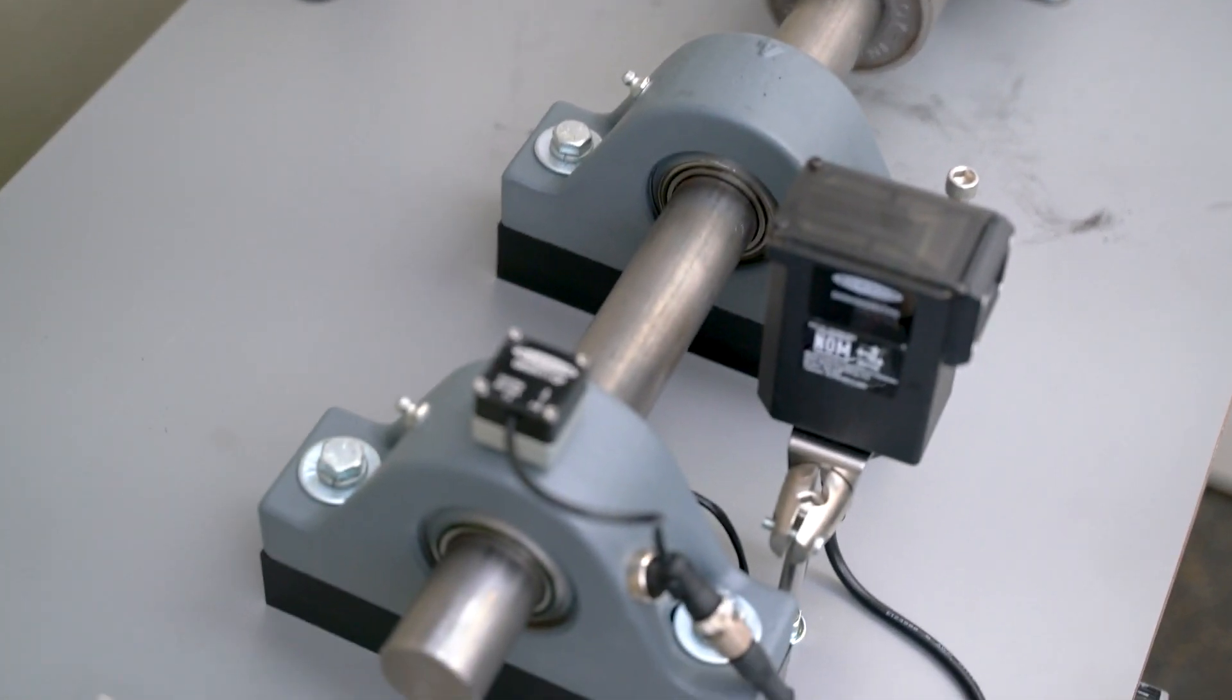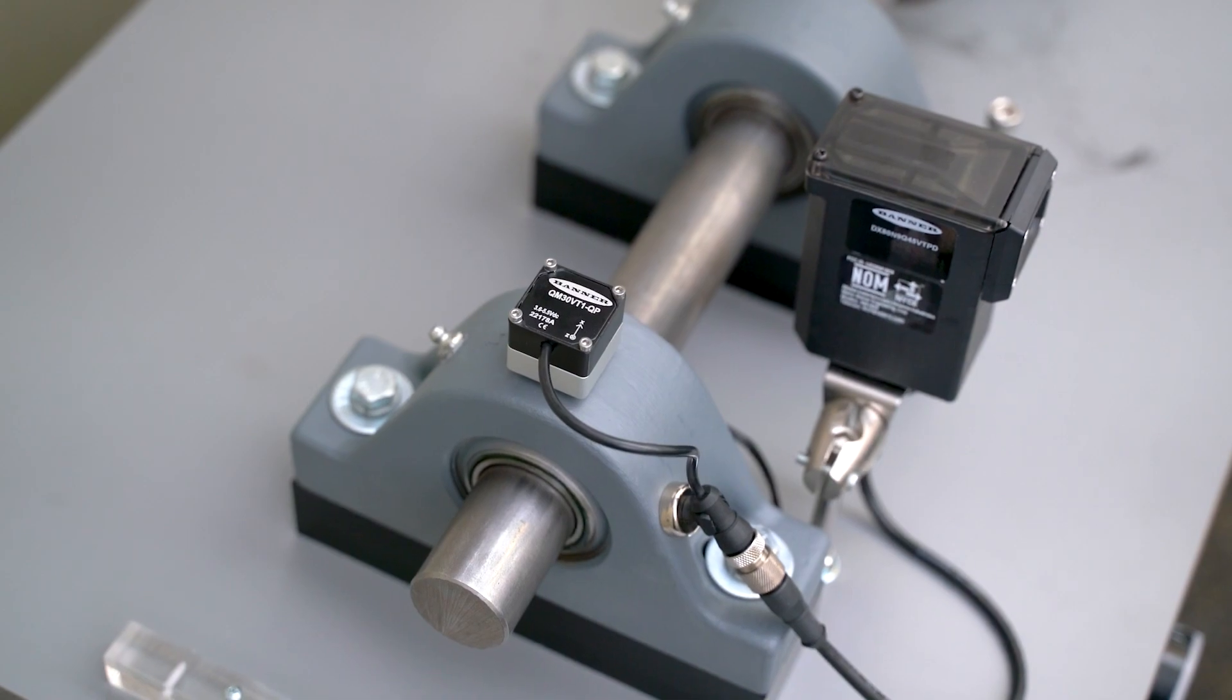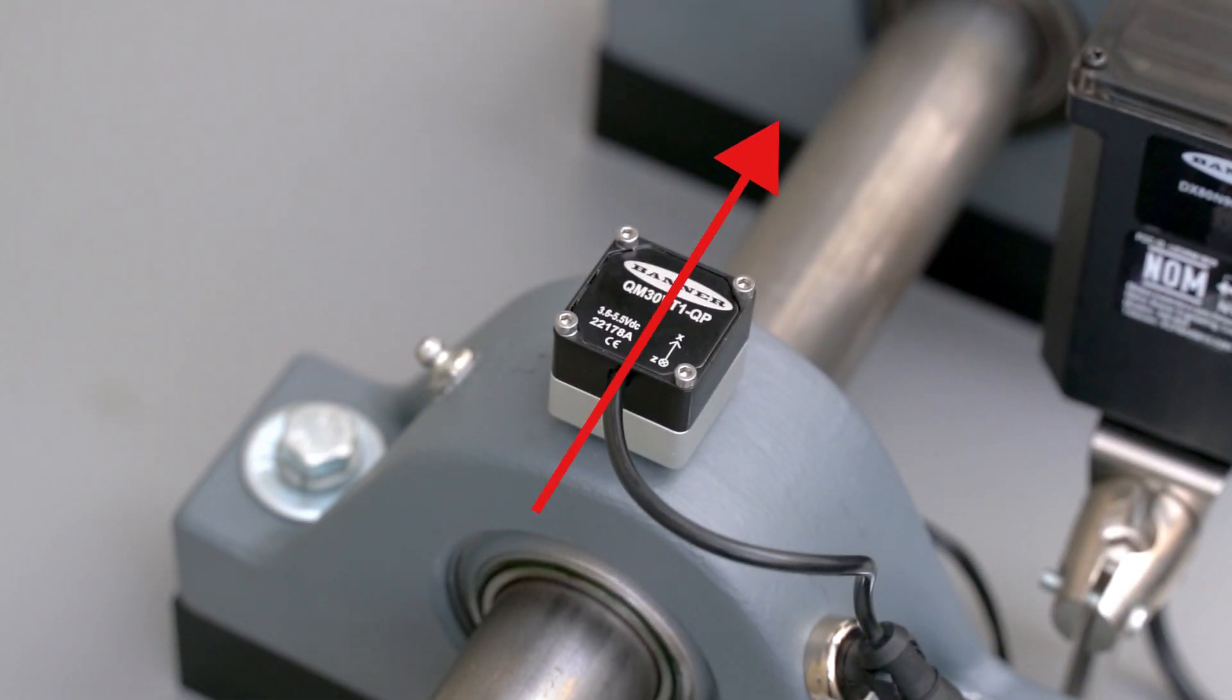When monitoring a pillow block bearing, the sensor should be mounted on top of the bearing with the x-axis parallel to the shaft passing through it.